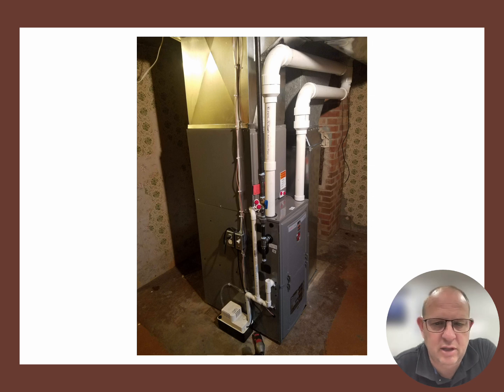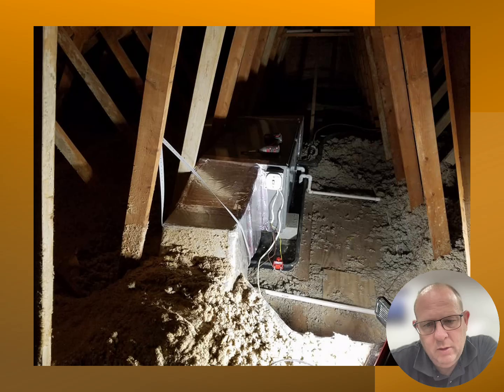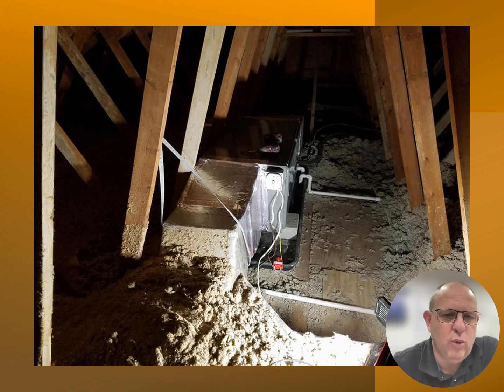So here's an attic installation that I have done. Notice that I have put a platform down for the auxiliary drain pan. And on that auxiliary drain pan, we notice a couple of safety devices. One's right there, and I'll highlight it in yellow. That is called an auxiliary drain pan overflow switch.